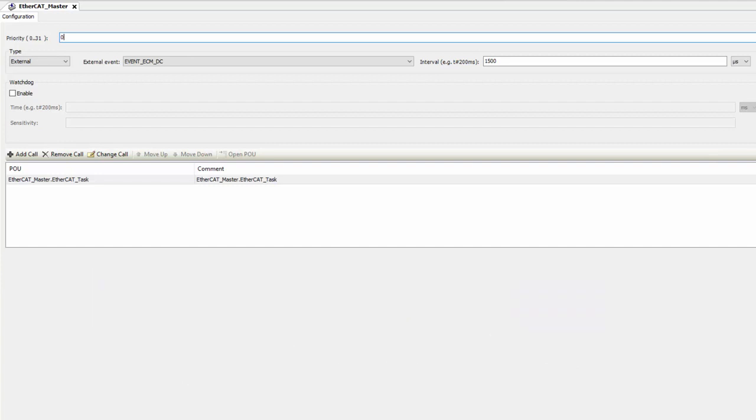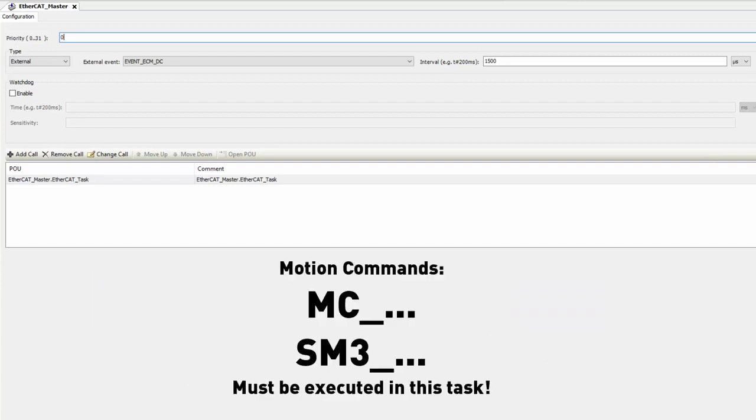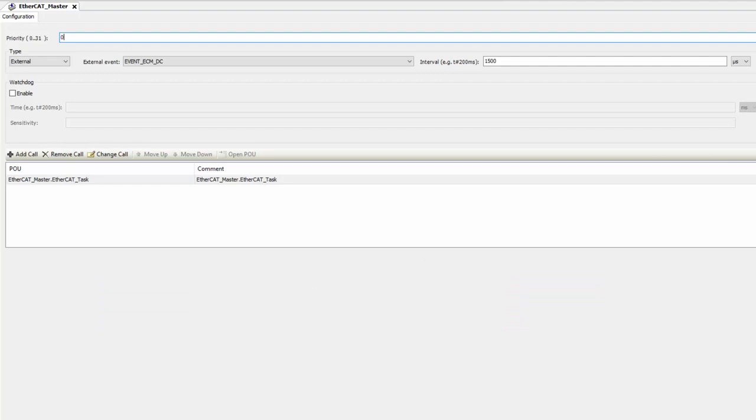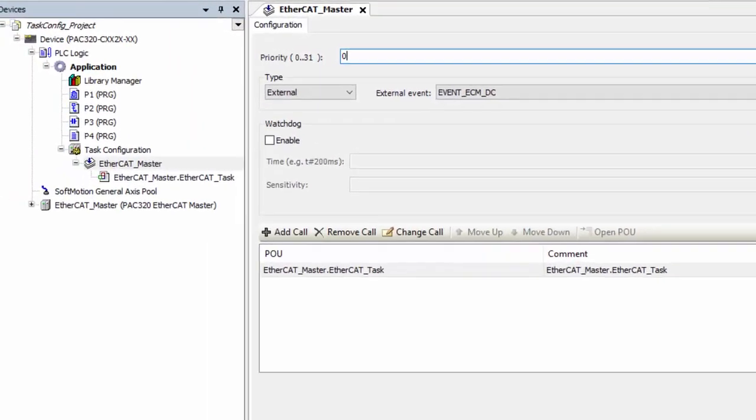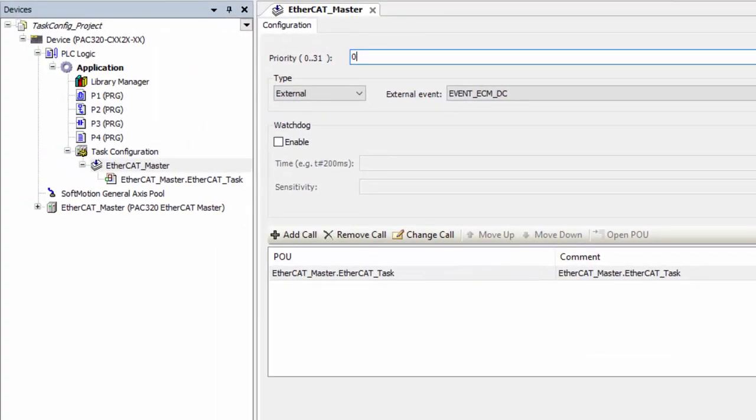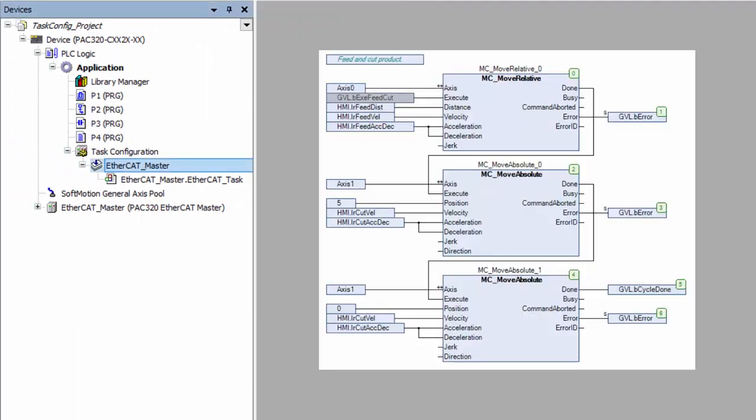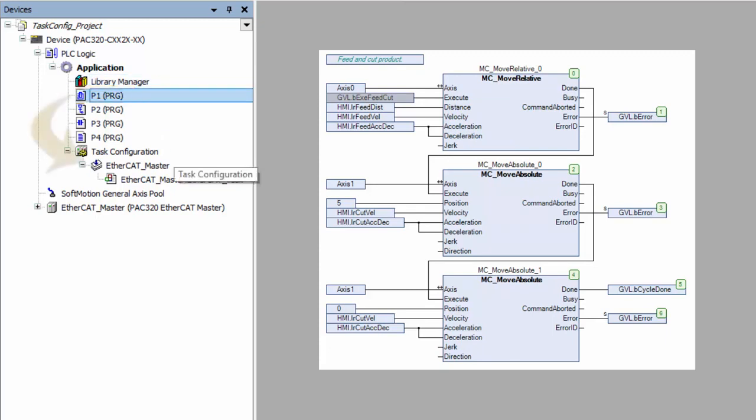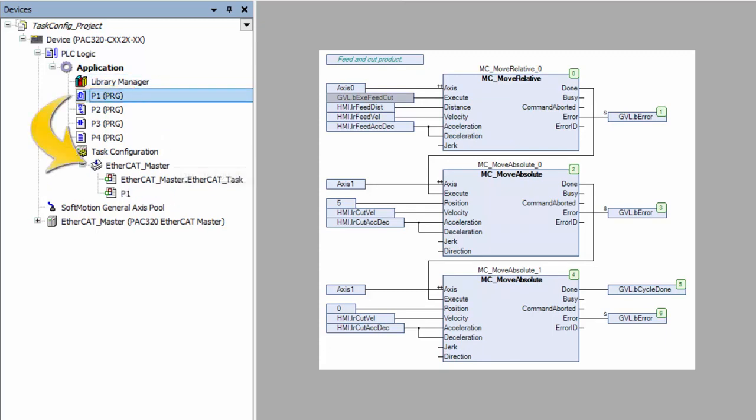In fact, motion commands starting with the prefix MC or SM3 must be called from this task. So how do I add motion logic to this task? Simple. Say we have a continuous function chart or CFC POU generically called P1, and it has all of our motion code. We simply click and drag it under that task.